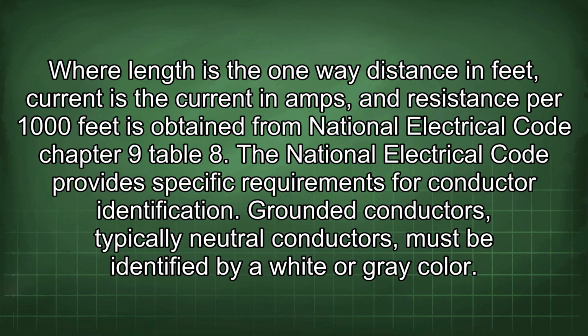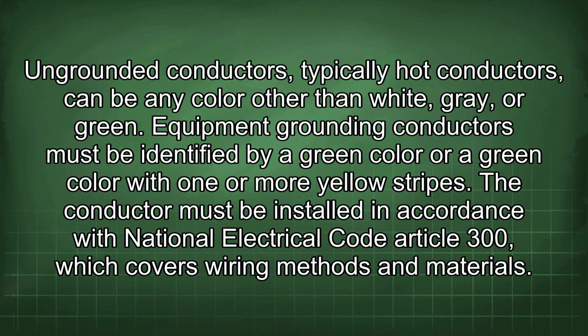The National Electrical Code provides specific requirements for conductor identification. Grounded conductors, typically neutral conductors, must be identified by a white or grey color. Ungrounded conductors, typically hot conductors, can be any color other than white, grey, or green. Equipment grounding conductors must be identified by a green color or a green color with one or more yellow stripes.